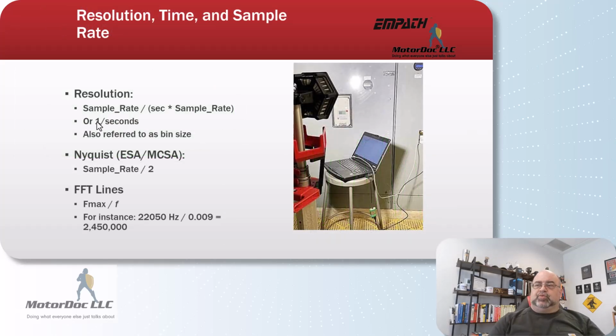Resolution is 1 over the number of seconds of data collected. This is the EMPATH unit. The EMPATH software we set up to collect across 120 seconds. We chop off the first 10 because sometimes there's a settling time if somebody just clips on and takes data. So we chop off that first 10 seconds. So we go 110 seconds, 1 over 110 is 0.009 for our resolution or our bin size.